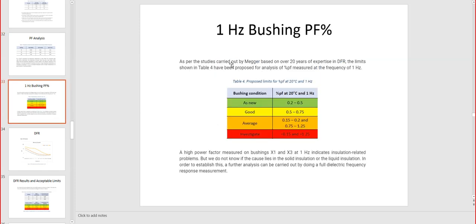1 hertz bushing power factor percentage, so bushing condition. This is from Megger. Megger and Doble are the 2 companies that have the most experience and the most database for the testing they did. And we can see here the bushing condition as new, good, average, and investigate. This comes from the actual Megger company. At 20 degrees and tested at 1 hertz, they recommend these values. As new will be between 0.2 and 0.5, good 0.5 to 0.75, average, and then investigate everything that's lower than 0.15 or greater than 1.25.